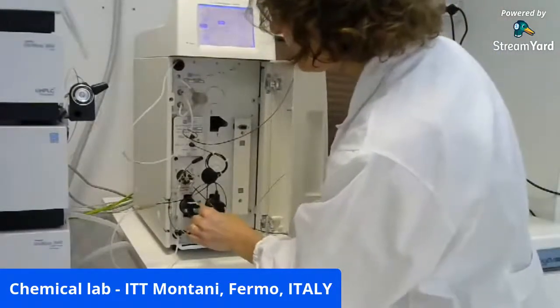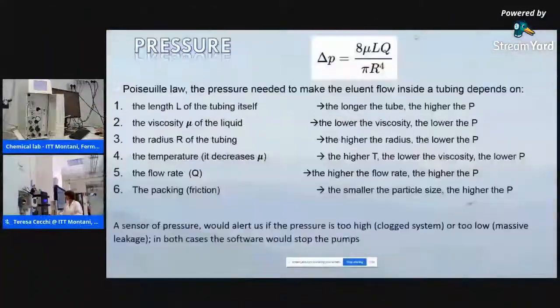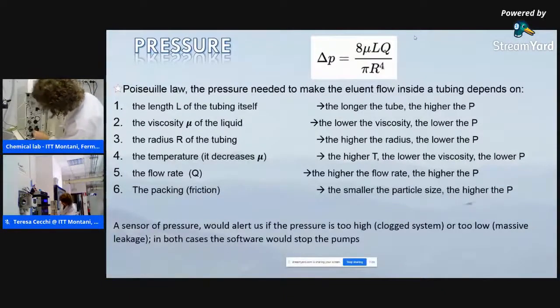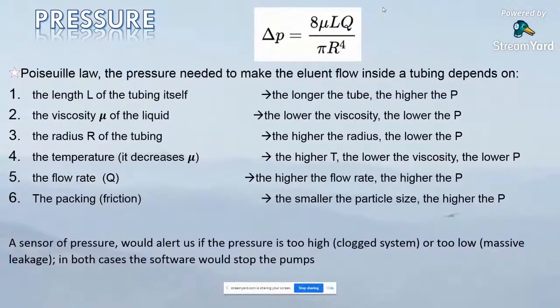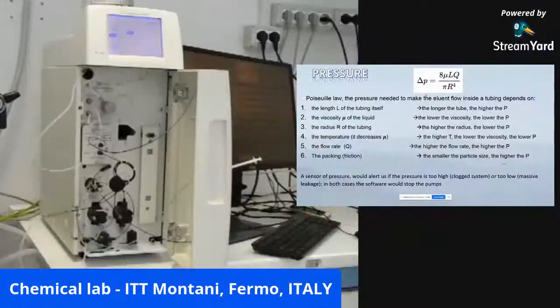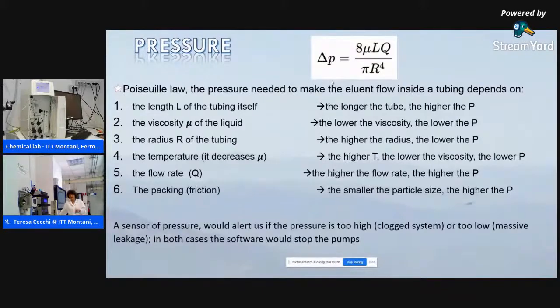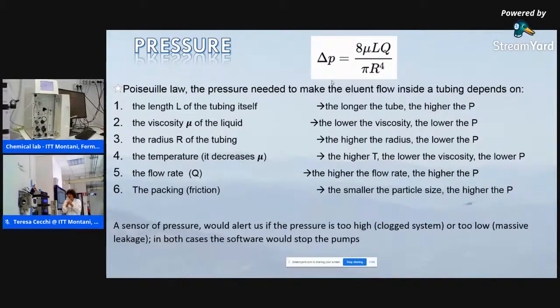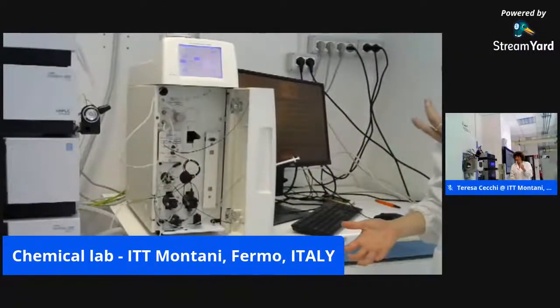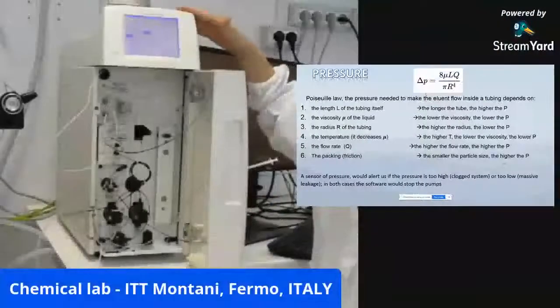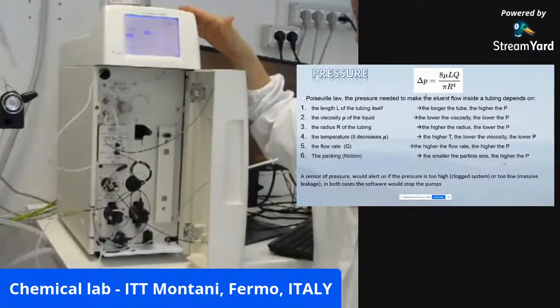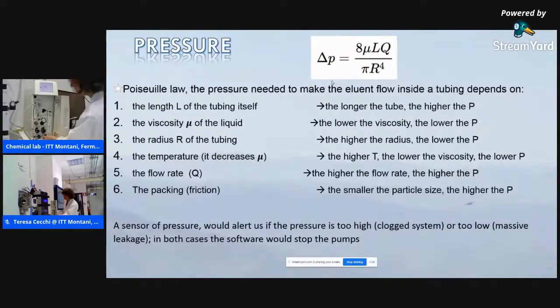Okay, if the purge valve is closed, we go on with the hydraulic circuit and we meet a sensor of pressure. This is the sensor of pressure. Why do we need to monitor the pressure? According to the Poiseuille law that you see here, if the length of the tubing increases, the pressure is higher. If the viscosity of the eluent increases, the pressure is higher. And the pressure increases also with the decreasing of the radius of the tubing, and it increases at lower temperature. So actually the system is a high pressure system because the column is finely packed. And so for this reason, we have to monitor the pressure.